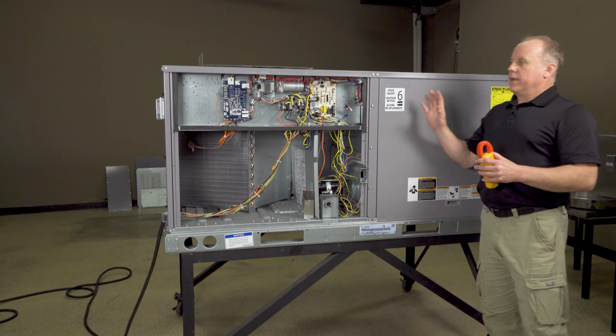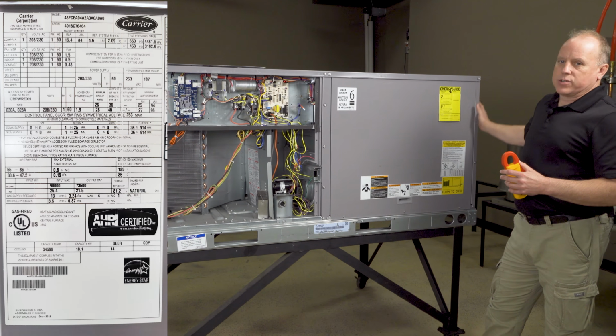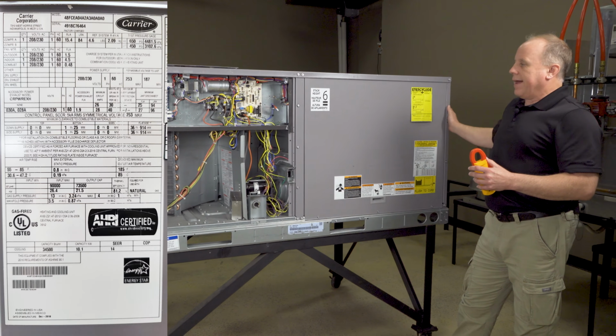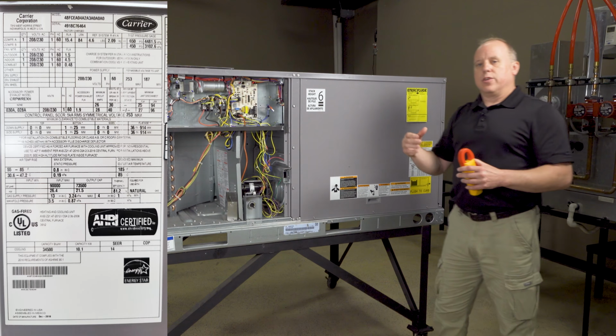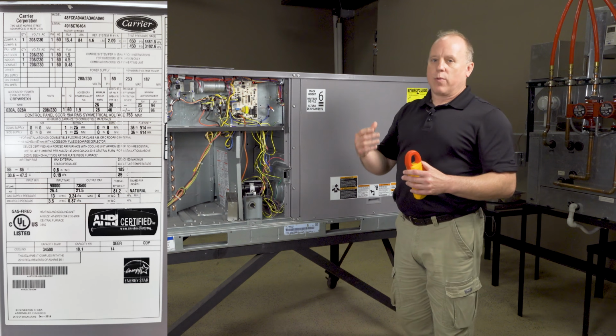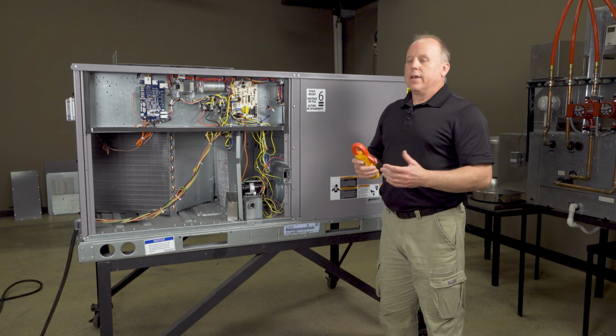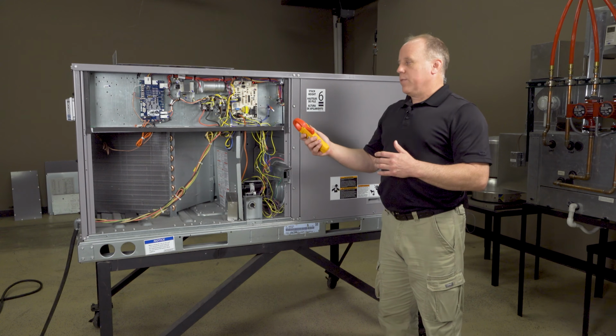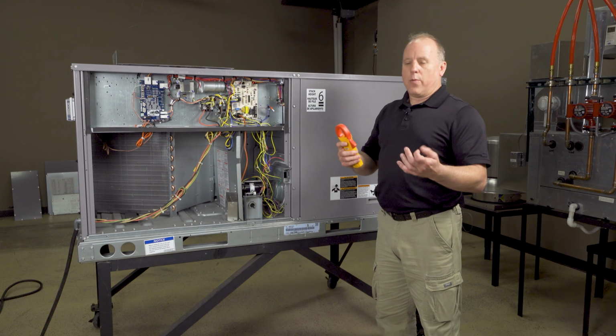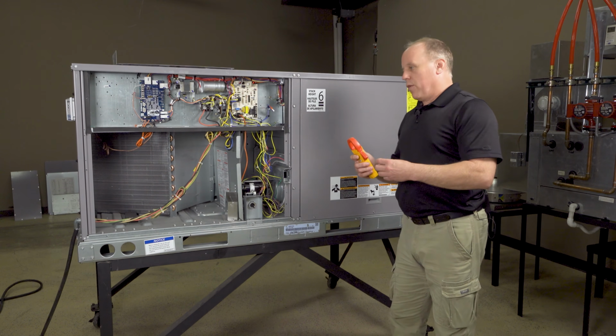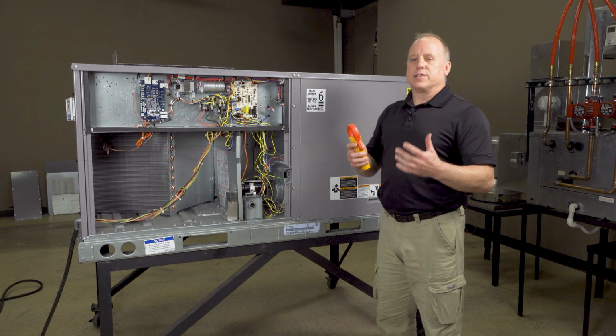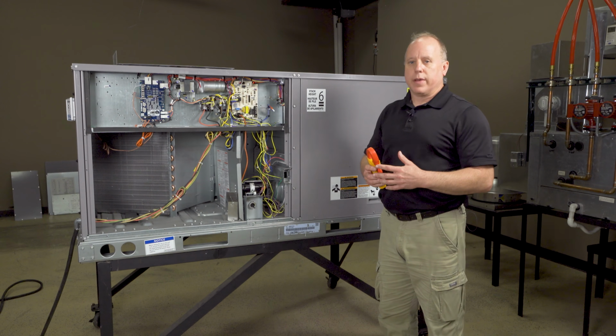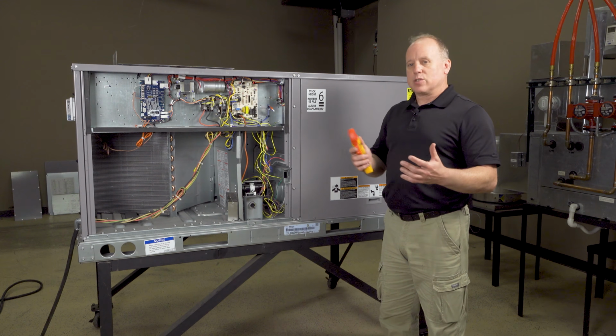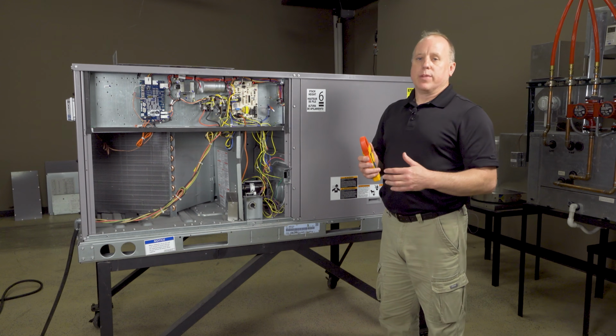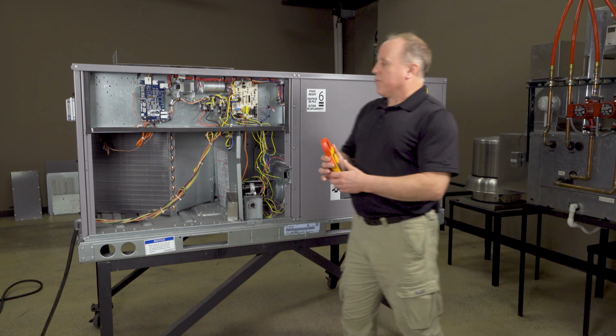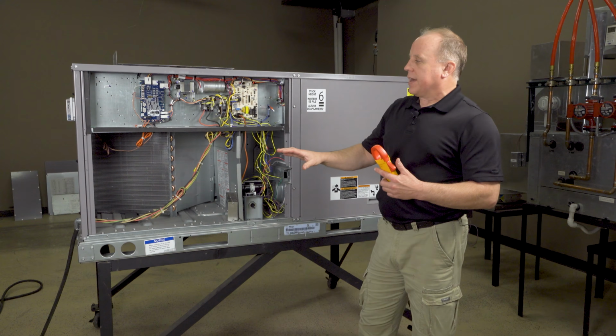So on the side of the unit, there's going to be a tag that's going to list all the running load amps, total amps, all the information of the unit, operational information that we need to reference to know what we should be running at. So that way we could take a look, see what the actual amp draws are on, whether it be a motor, the compressor, the blower motor, and make sure that they're at least operating within range of where they should be. And that'll let us know if there's maybe something else going on, if there is a problem with that amp draw. So first off, we're going to locate our wires for what we're talking about.